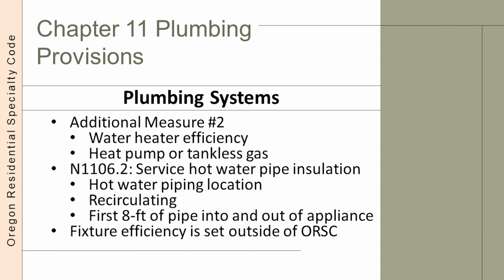Moving on to plumbing systems, Chapter 11 has only a few plumbing requirements. Under additional measures, if selecting additional measure number 2, high efficiency water heaters are installed. This usually entails a heat pump water heater or a condensing gas fired tankless water heater. Prescriptive requirements are limited to installation of piping for service water heating. If the pipe is not fully within the thermal envelope, the pipe must have R3 insulation. Recirculating systems also require R3 insulation on the portions of the pipe with circulating hot water. And the first 8 feet of pipe, both into and out of a water heater, requires insulation as well. High efficiency, low flow fixture requirements are found outside of the ORSC. These are found both within state appliance standards and the Oregon Plumbing Specialty Code.